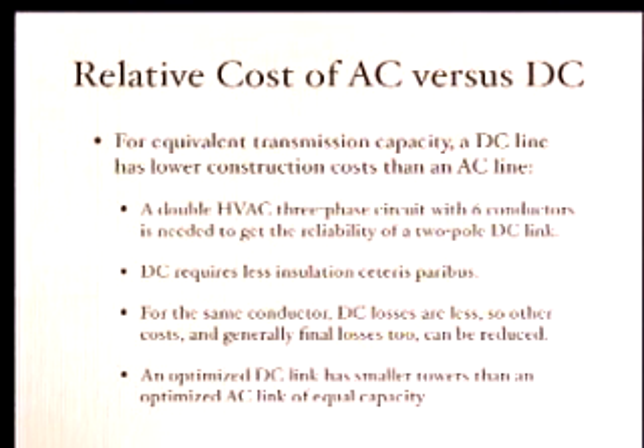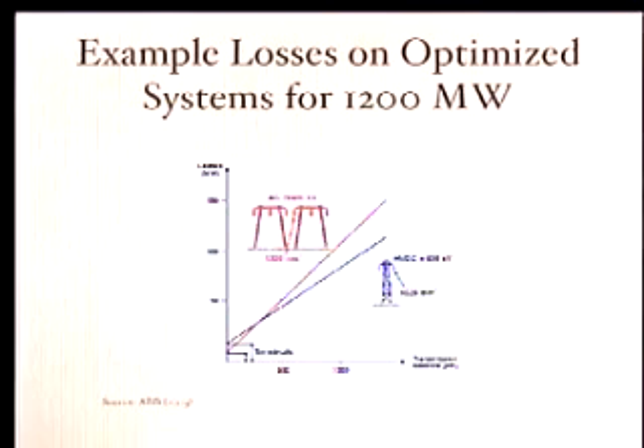If you wanted to compare the cost of AC versus DC, as I had the picture up a while ago, DC requires smaller transmission towers, has less power losses for an optimized system, and requires less insulation. On the other hand, it has the extra cost of the terminals. So there's a crossover point where once you get beyond a certain distance, about 300 kilometers, it's cheaper to use DC rather than AC.